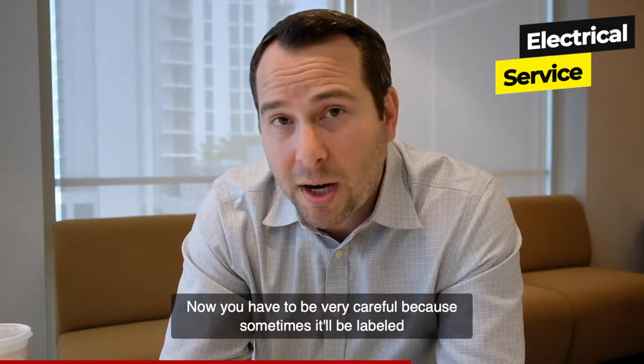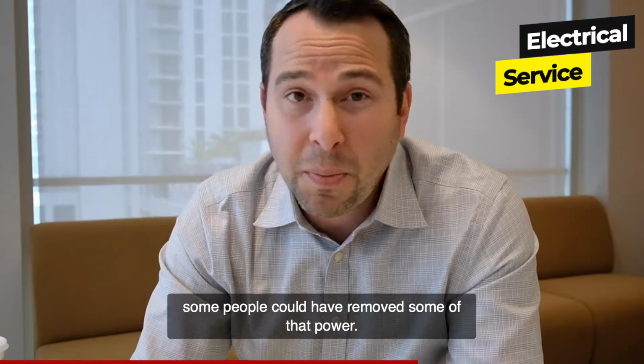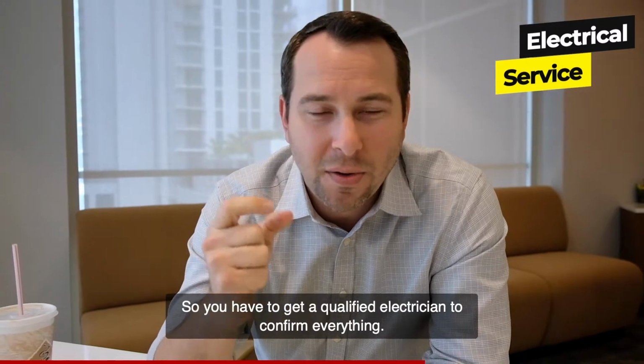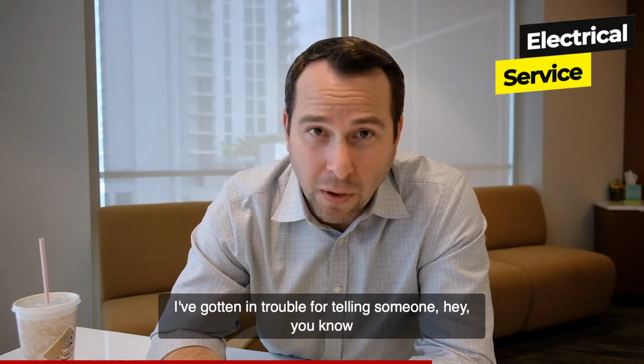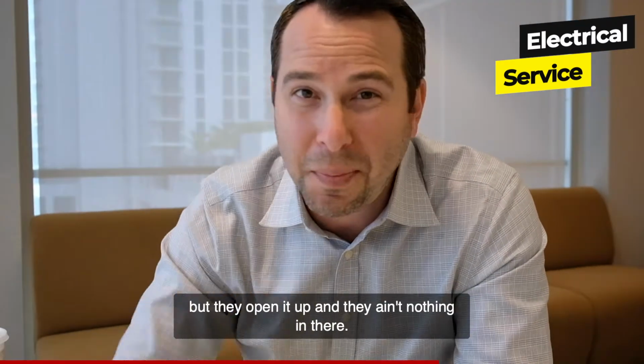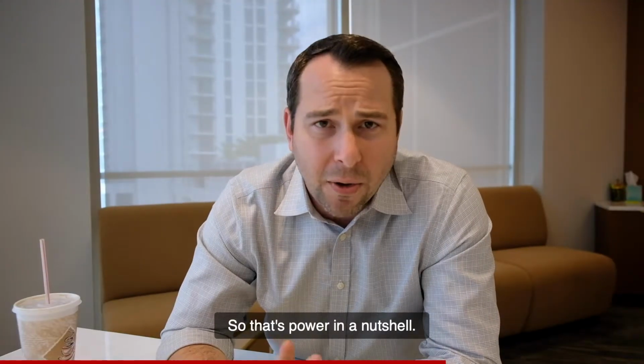Now, you have to be very careful because sometimes it'll be labeled, but along the way, as the years go on, some people could have removed some of that power. So just because it says it doesn't mean the wires are actually there. So you have to get a qualified electrician to confirm everything. I've gotten in trouble for telling someone, hey, it says it right there, it's 400 amps, but they open it up and there ain't nothing in there. So you gotta be really careful and you gotta know what you're doing. So that's power in a nutshell.